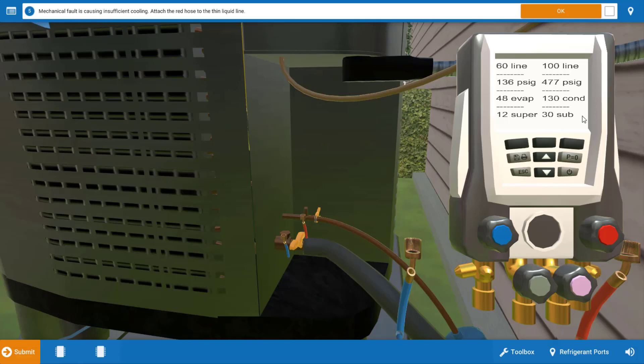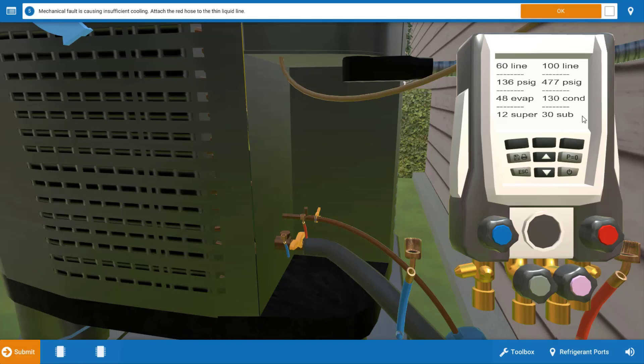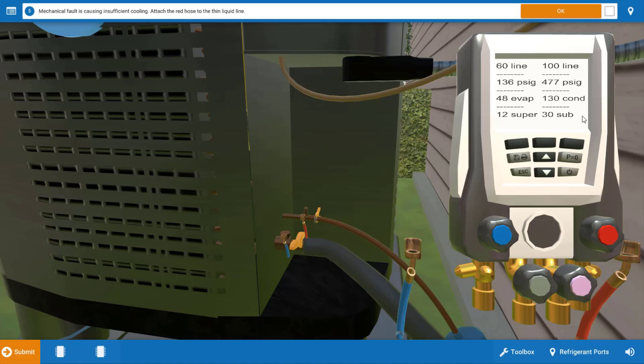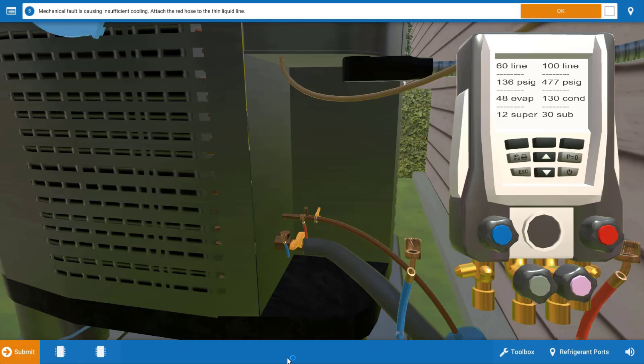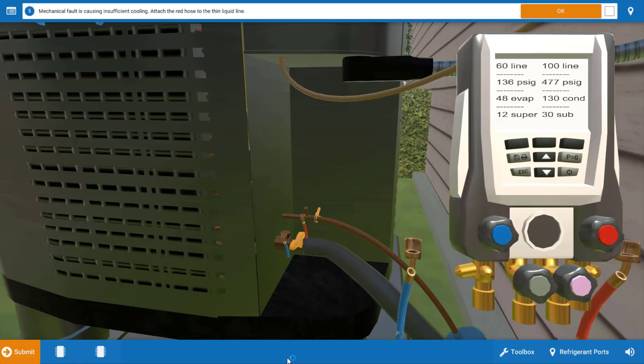Now we want to look at our subcooling. This unit has a TXV metering device so our charging indicator here, or the way we actually accurately assess the charge as well as correct the charge, would be to measure subcooling. If you look on the unit data plate in most cases there'll be a target subcooling margin listed and in this particular unit it's 13 degrees. In the event that you can't locate the target subcooling on the data plate you may need to look at the installation booklet that came with the unit. But what we do know is that with a target subcooling margin of 13, 30 is way too high. It's excessive and this indicates an overcharge of refrigerant. That is our telltale sign, the subcooling margin.